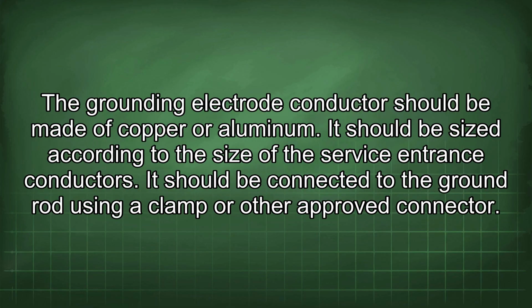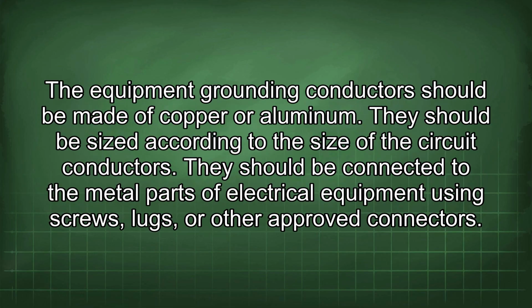The grounding electrode conductor should be made of copper or aluminum. It should be sized according to the size of the service entrance conductors. It should be connected to the ground rod using a clamp or other approved connector. The equipment grounding conductors should be made of copper or aluminum. They should be sized according to the size of the circuit conductors. They should be connected to the metal parts of electrical equipment using screws, lugs, or other approved connectors.